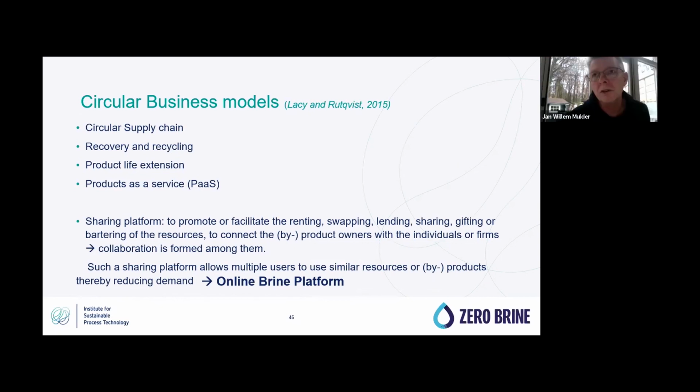In the situation of Lamb Weston, the company owns and operates their own wastewater treatment. So we don't play a role in the wastewater treatment activity, but they deliver the effluent treated wastewater to us, and in our own facility, on a DBFO basis, we treat that water further to produce demineralized water for them, and we deliver it back to the company. So the reuse plant is owned by us and operated by us.